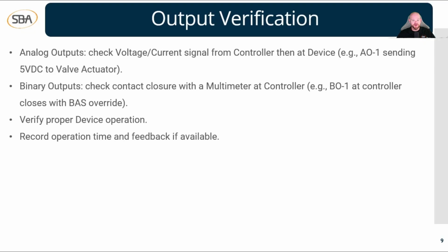So now that we've covered input verification, let's talk about output verification. Again, same deal here. We've got analog and binary outputs. So with analog outputs, we're going to check voltage or current signal from the controller. So we're checking the terminal screws on the controller to make sure that we're getting a voltage or a current sent out from the controller. If we do there, then we'll go to the device that we're controlling and we'll check it there as well. And the example here would be like an analog output 1 sending a 5-volt DC signal to like a hot water valve actuator. So we would check at the controller, make sure we're getting 5-volt DC out of that analog output 1.